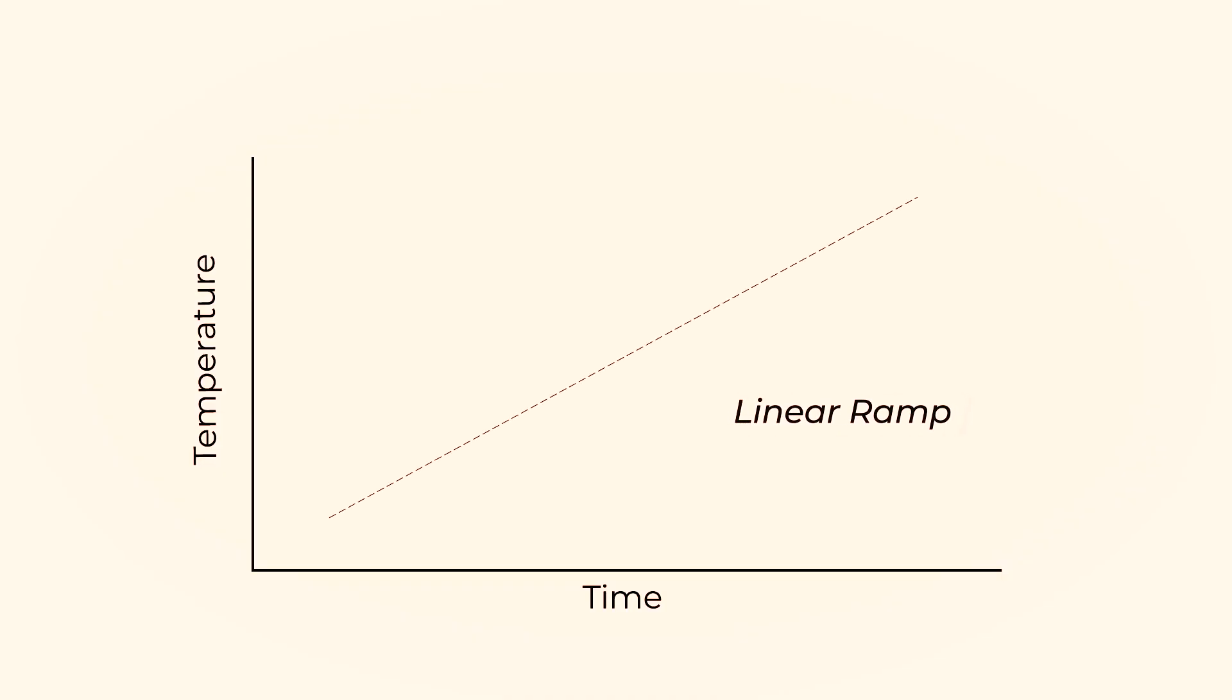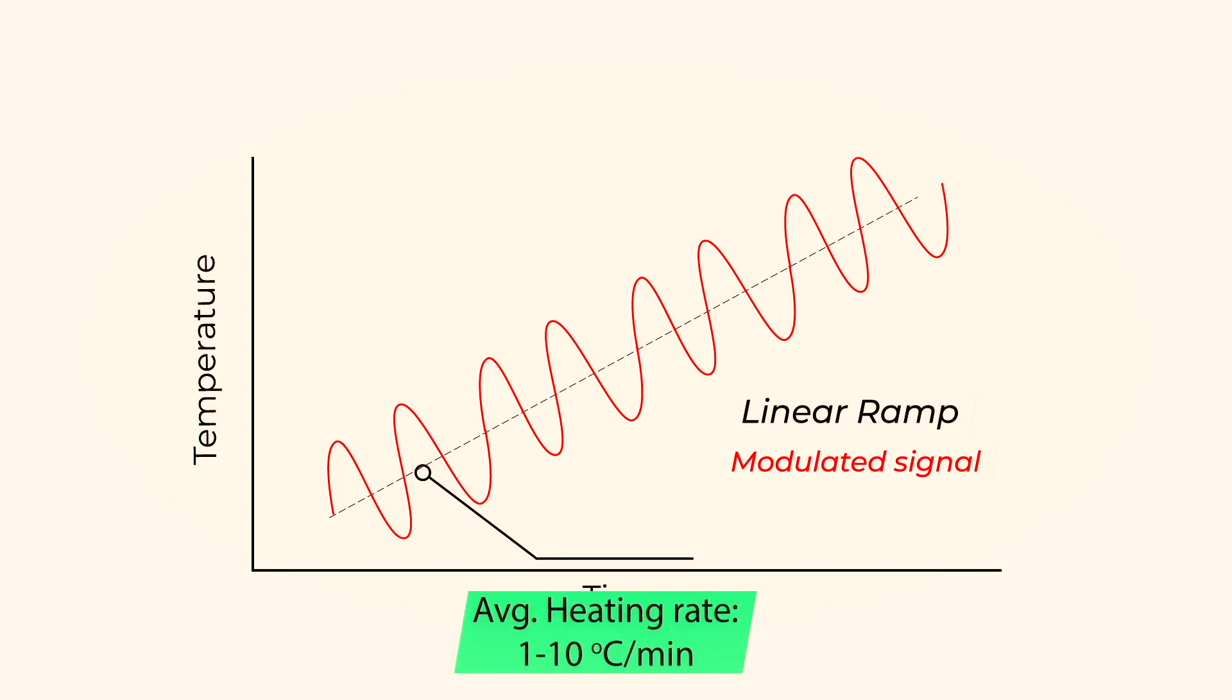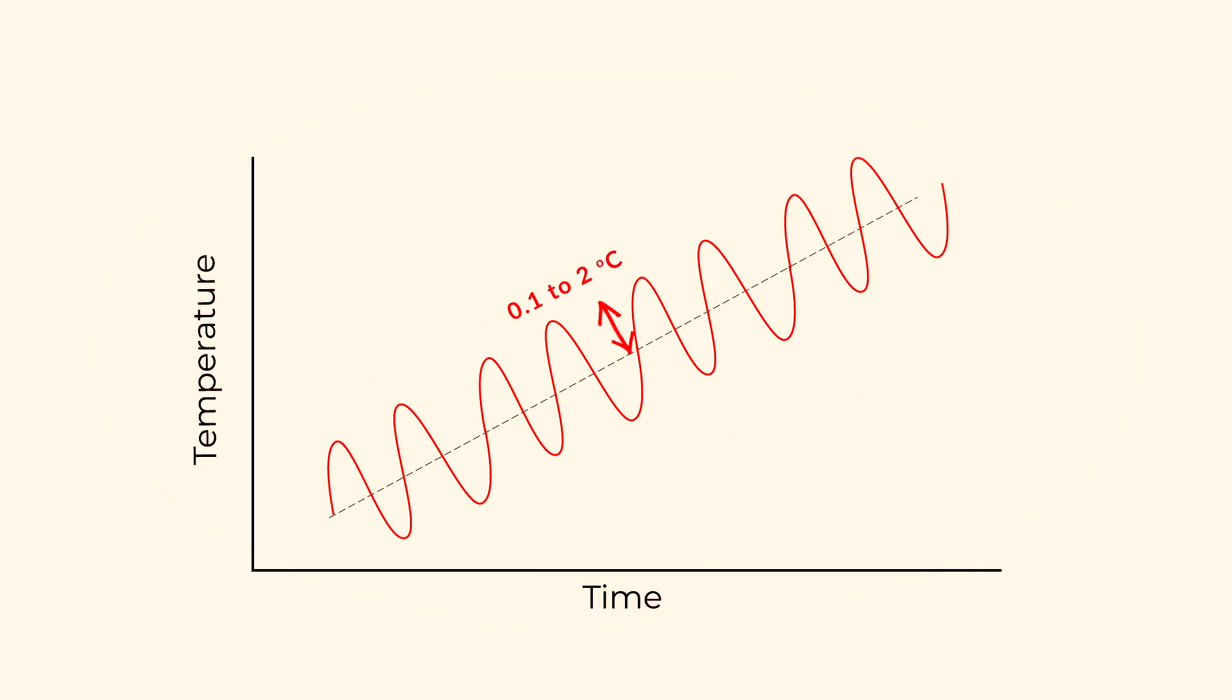In MDSC, a different heating profile is applied to the sample and reference. Specifically, a sinusoidal modulation is overlaid on the conventional linear heating or cooling ramp to yield the profile in which the average sample temperature continuously changes with time, but not in a linear fashion. There are three main parameters which are used to control the MDSC experiment. The first is the average heating rate, which is kept between 1 to 10 degrees C per minute. A temperature modulation period between 30 to 100 seconds is maintained. And the last parameter is the temperature amplitude, which is generally around 0.1 to 2 degrees C.